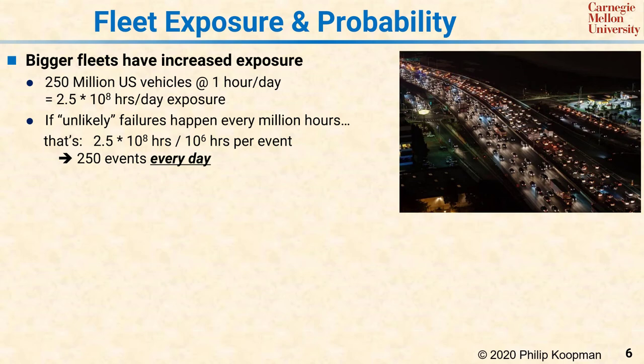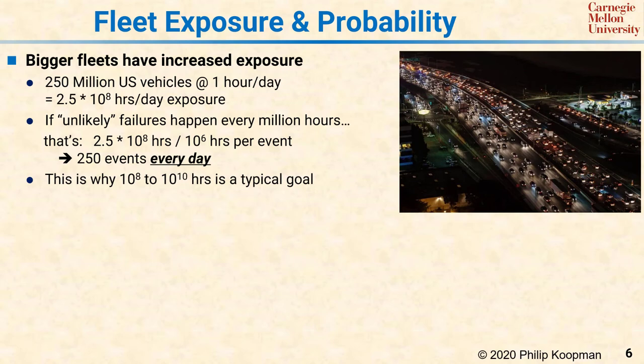This is why a permissible failure rate of once every million hours is generally not acceptable for a catastrophic mishap. It is common to see much more stringent goals: the chemical process industry uses every 100 million hours for a catastrophic event, in aviation it's every billion hours, and in rail it's every 10 billion hours.